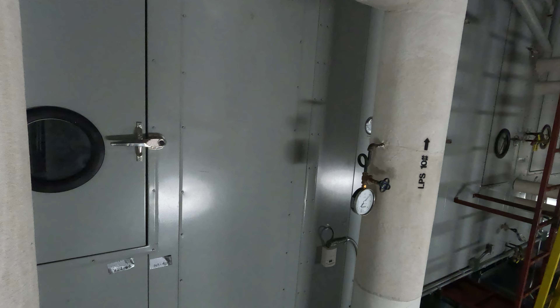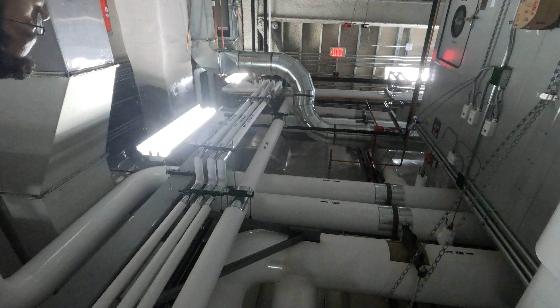So the newer buildings, ours included, have four air handling units. This is one of four, and they're all connected together with one common ductwork, the silver wrapped one up there. All four units serve the entire building all the time, so for energy efficiency, all the fans run at half speed. If we need to take one down for maintenance or if there's a service issue and it shuts off, the other three will automatically speed up to compensate. So there will never be a lack of air movement, and nobody in the labs will be inconvenienced because we have to shut equipment off. That was one of the big pluses of this particular building.